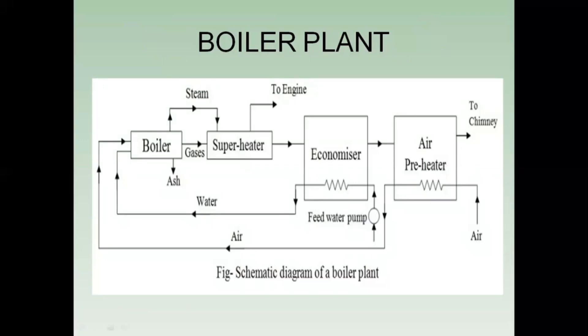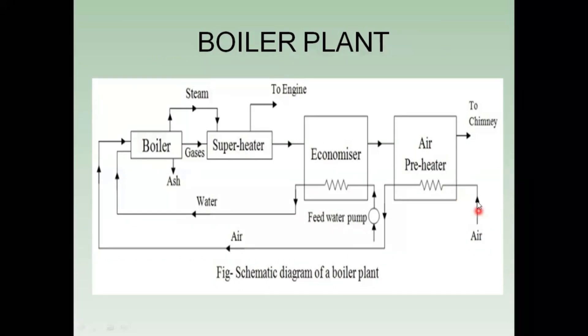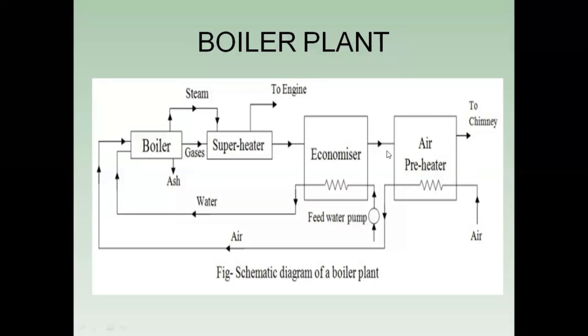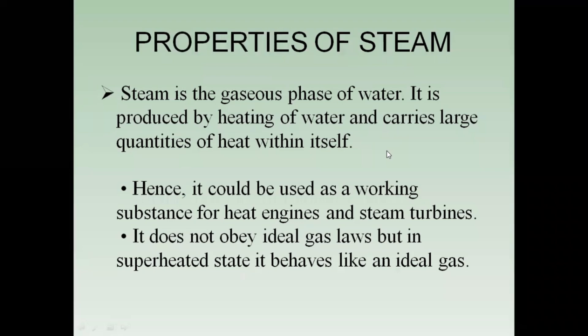This is the schematic diagram of a boiler plant. We see that firstly the air is entering the air preheater, where the air is preheated by the use of exhaust flue gases. Then from this direction the air is going to the boiler. Similarly, by the use of the feed water pump, the water is flowing to the economizer, and then from the economizer it is going to the boiler. The steam produced from the boiler then goes through the superheater, where the superheater heats the wet steam to dry steam, and then it goes to the engine.